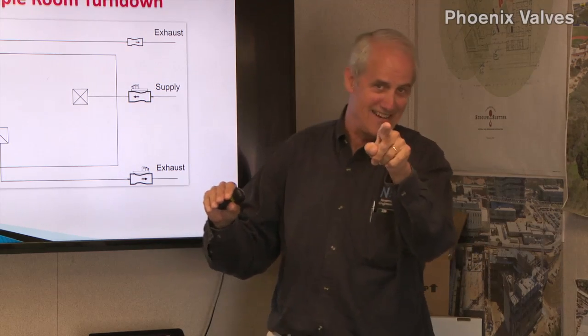If it beeps and flashes fast, beep, beep, beep, beep, then the problem is low pressure drop. There's not enough suction. Somehow the hood isn't feeling enough suction. If it's a slower beep, beep, beep, beep, that means someone has probably raised the sash. The hood's only designed to an 18-inch operating height. That's where the sash stop is. If someone defeats that sash stop and takes the sash higher, you're going to get the slower beep. Unless you also lose fan at the same time. The low fan alarm overrides all alarms, so the fast beeping will trump all others. If you have a fast beep, you might also have a slow beep, but there's no way to know it unless you fix your fan problem.